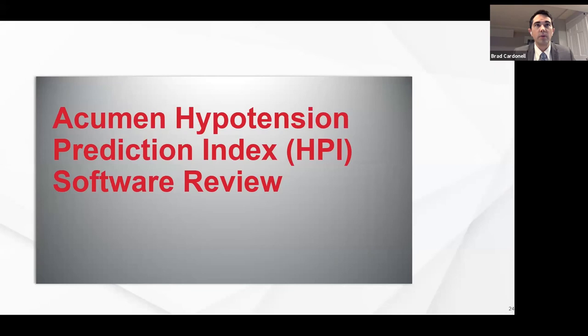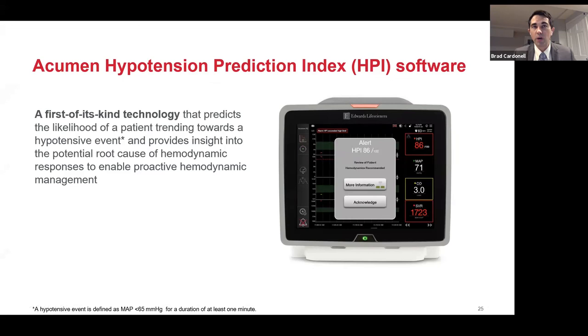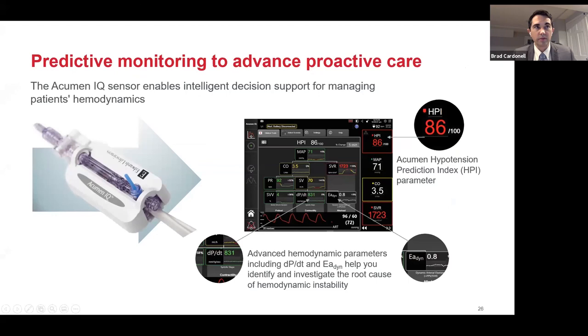Let's take a clinical look at the Acumen Hypotension Predictive Index. Acumen HPI software is a new technology that predicts the likelihood of a patient trending towards a hypotensive event, using that insight and additional parameters to find the root cause and proactively prevent hypotension before it occurs. It consists of an Acumen IQ sensor or transducer and an advanced hemodynamic monitor, with secondary parameters such as cardiac output, cardiac index, EA-dyne, dP/dT as a measure of contractility, stroke volume variation, pulse pressure variation, and the HPI number.